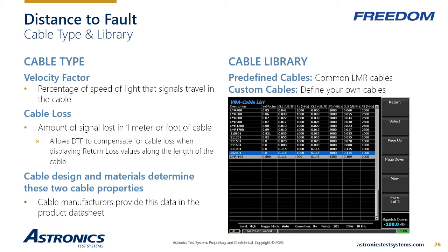The cable loss parameter allows the tool to adjust the displayed return loss value to compensate for cable loss at a distance. As an example, an antenna at the end of a cable might have a measured return loss of minus 35 dB when measured from the far end of the cable, but the instrument calculates that the cable has 5 dB of loss for that length of cable and displays a return loss value of minus 25 to account for this cable loss. For the 5 dB of signal that's lost before the signal reaches the antenna, and the 5 dB of signal lost when the reflected signal travels back towards the instrument.